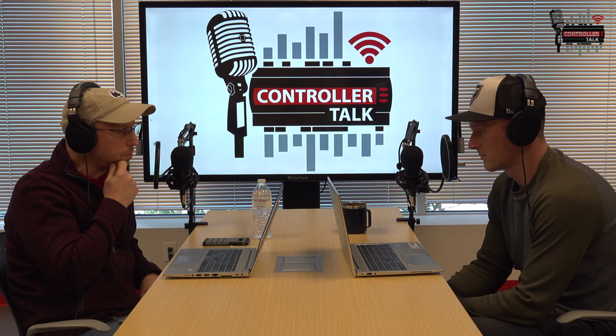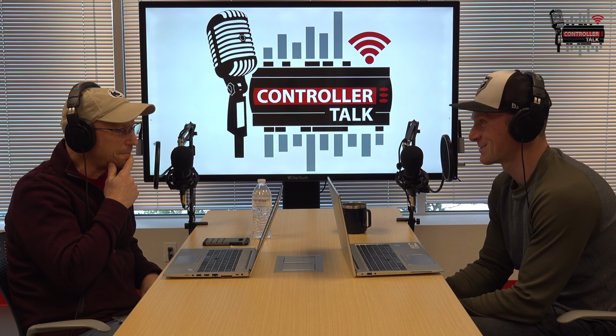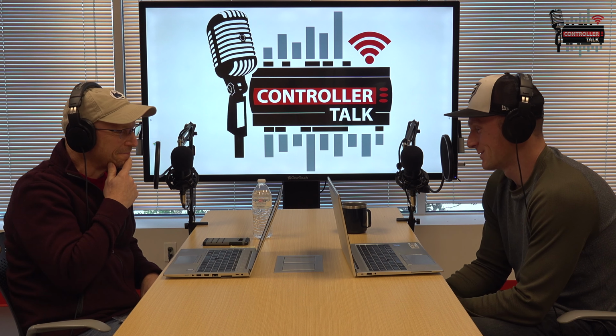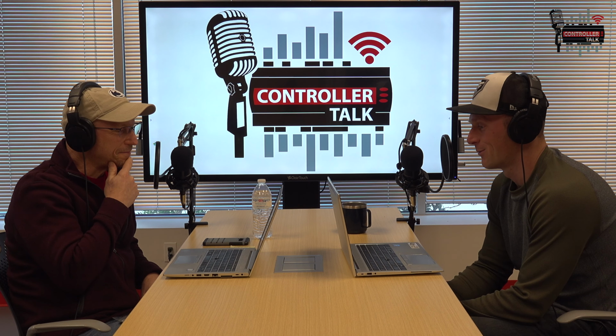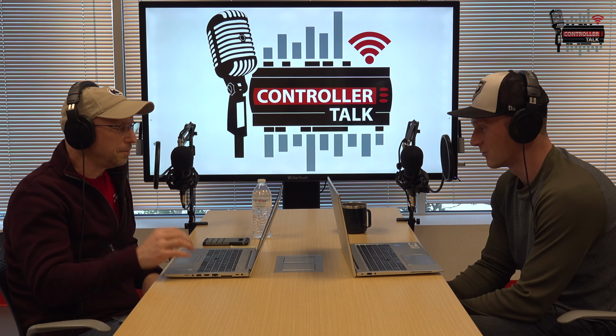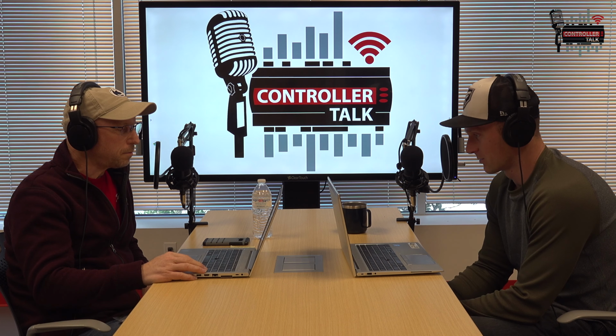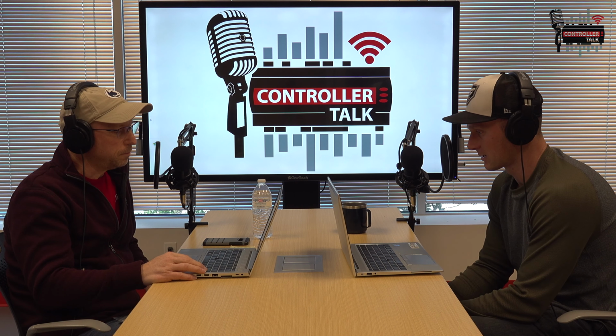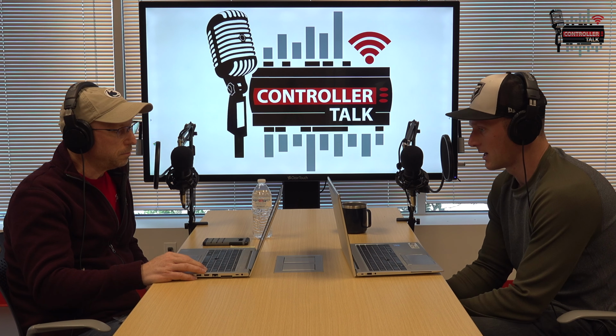And then in the last 15 years or so, we've seen more of a shift to digital compressors. I won't steal the thunder on the manufacturers from you, but I think most guys, if you're listening to this podcast, you've probably seen them, heard them, come across them before. We're dealing with these digital compressors where you're cycling unloader solenoids at a pretty frequent rate. And for us, using this VO option in our program gives us that ability to do that.